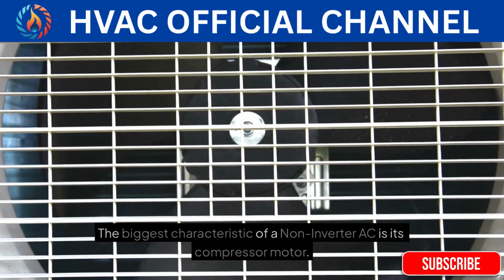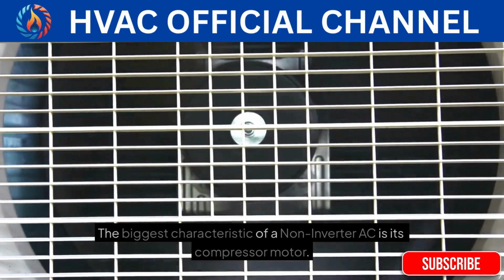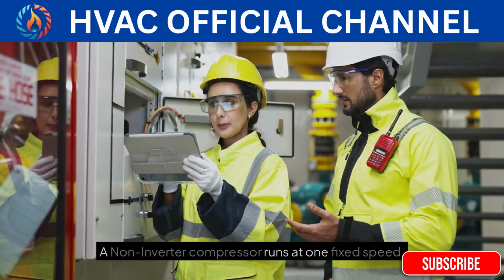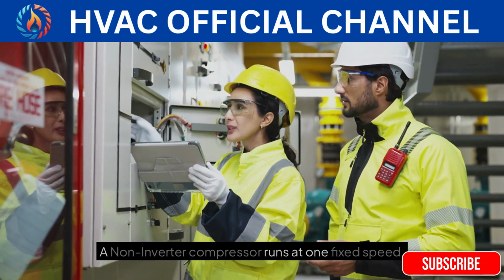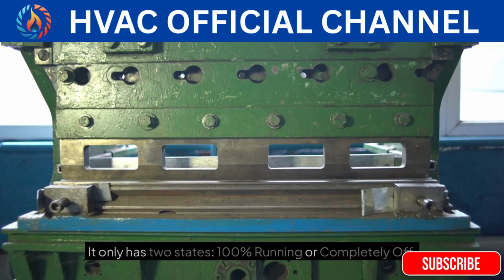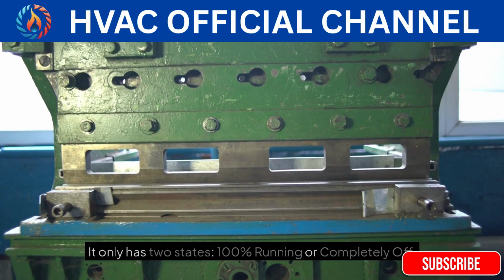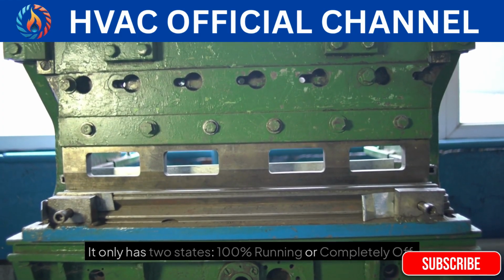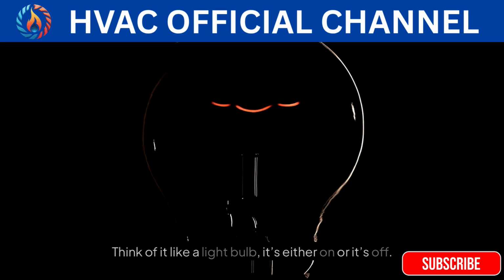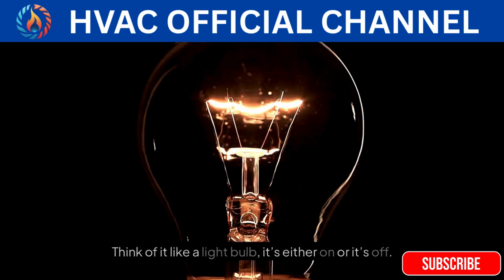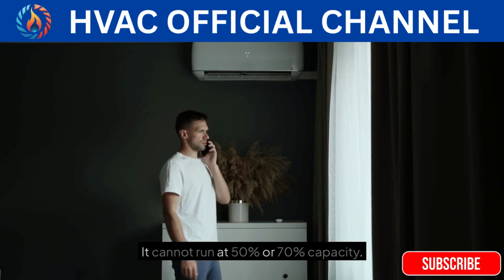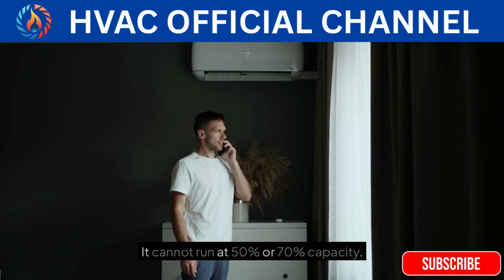The biggest characteristic of a non-inverter AC is its compressor motor. A non-inverter compressor runs at one fixed speed. It only has two states, 100% running or completely off. Think of it like a light bulb, it's either on or it's off. It cannot run at 50% or 70% capacity.